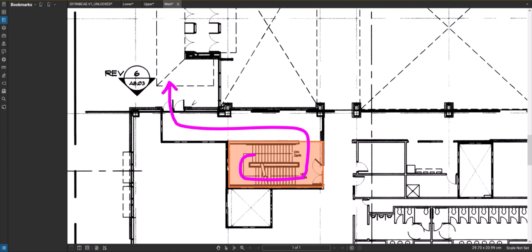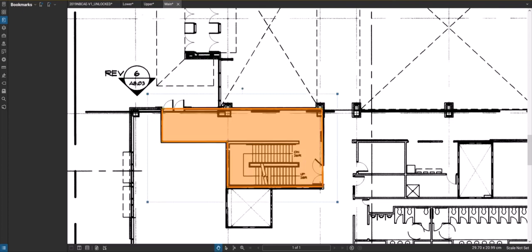So what they've done here is they've created a corridor, and this corridor would have the same fire separation as that stair. If I dug into the drawings, in this building there would be a 2-hour fire separation around the stair, based off the fire separation requirement of the floor. You'll see on this main floor there's no wall or door here, because this corridor has become part of that stair, and that fire separation is around this entire perimeter. So you are in that protected zone until you get to the exterior there.